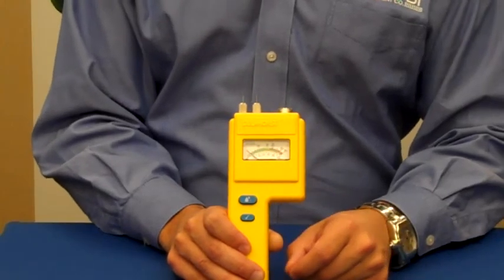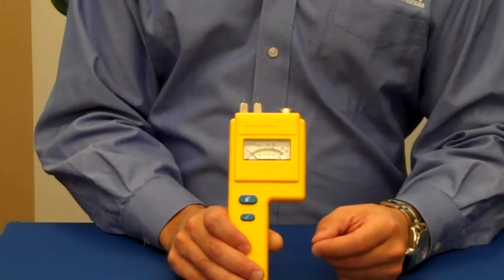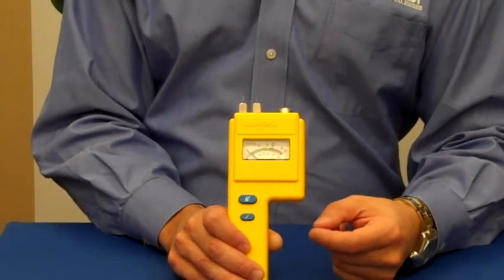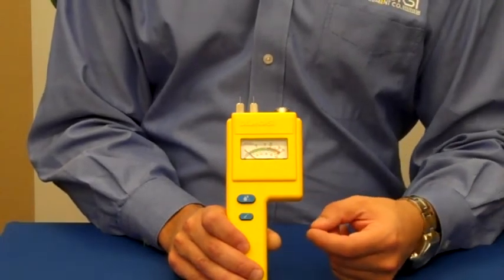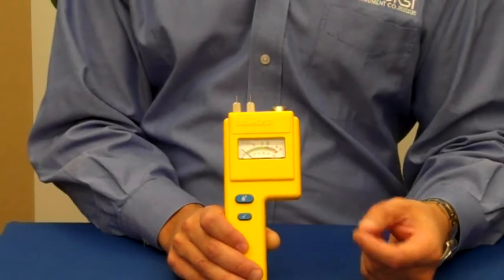The reference scale can be used for insulation, drywall, and concrete. And the 0 to 100 doesn't indicate percentage moisture content, but it does indicate whether or not there's more or less moisture in a particular area. So it can be used as a comparative basis or a comparative scale.